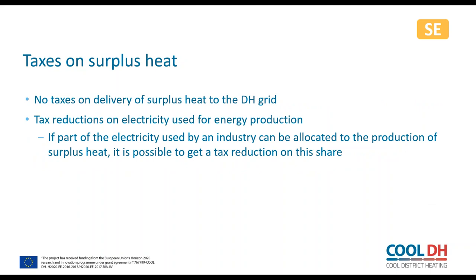And then definitely it's easier to pick up the heat and utilize it because there are no taxes on delivery of surplus heat to the district heating grid. So that is a positive thing. You can use more of the total capex to invest in the heat pump, in the system connection, and still have a good business case on that. And then on top of that, there are tax reductions on the electricity used for energy production. So that is two things that are promoting the pickup of surplus heat on the Swedish side.